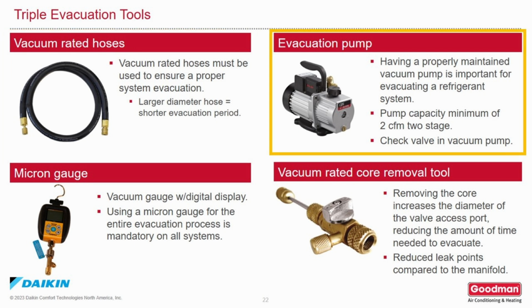A properly maintained vacuum pump is essential in evacuating a refrigerant system. You should have a 2-stage pump with a minimum capacity of 2 CFM. Please beware of using large pumps. If you evacuate too quickly, ice can form inside the pipe, causing false readings on your vacuum gauge. Check the valve and the oil level in your vacuum pump.